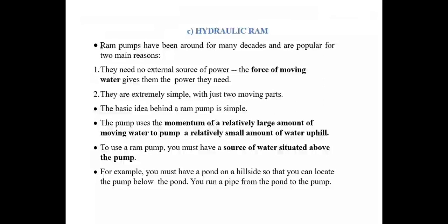Hydraulic ram or ram pumps have been around for many decades and are popular for two main reasons. First, they don't need any external source of power, and they are extremely simple with just two moving parts. The basic idea behind a ram is very simple: it uses the momentum of a relatively large volume of moving water to pump a relatively small volume of water uphill.